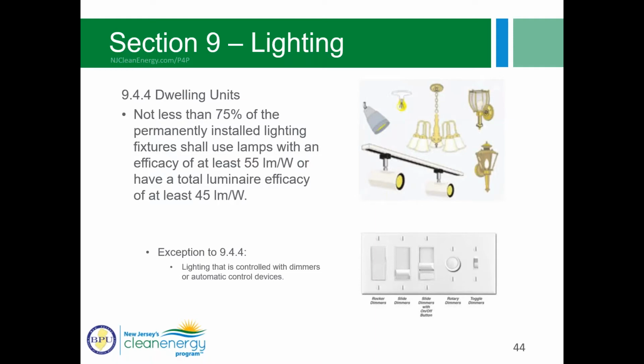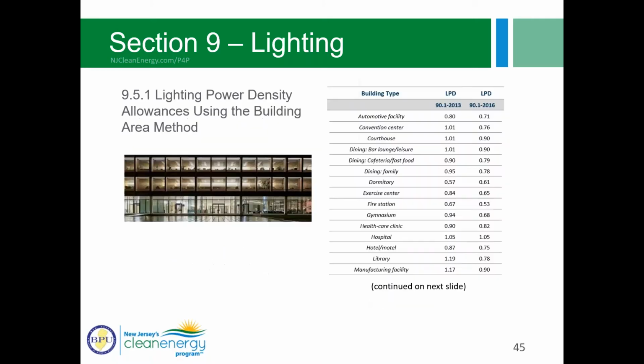This was a new requirement that says not less than 75% of permanently installed fixtures shall use lamps with an efficacy of 55 lumens per watt or have a total luminaire efficacy of at least 45 lumens per watt. So just be mindful of which lumens per watt value you are citing for your project. And the exception for this would be anything with dimmer controls or automatic control devices.